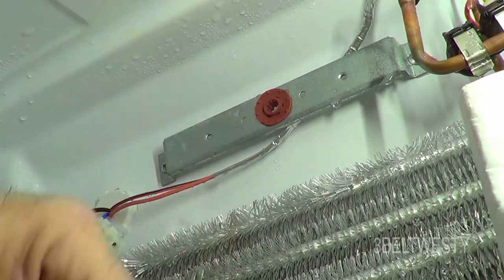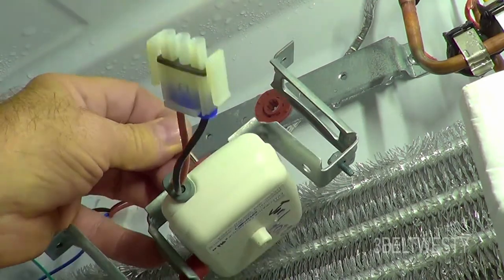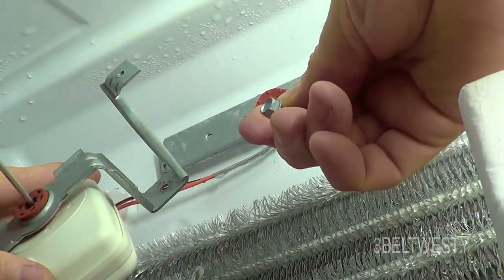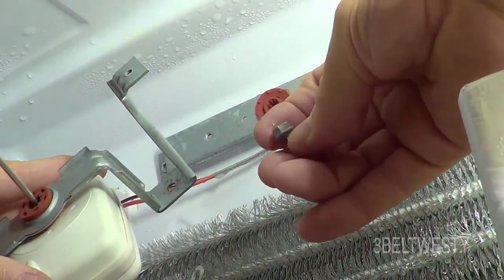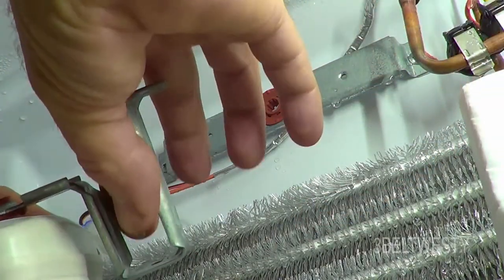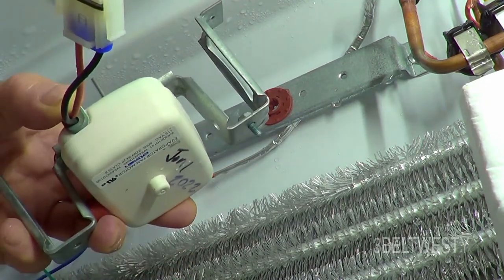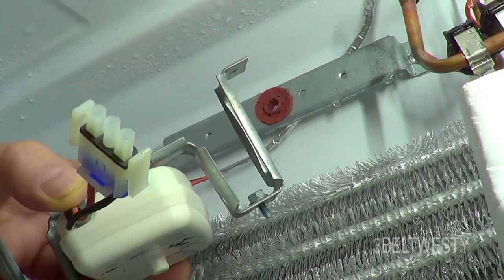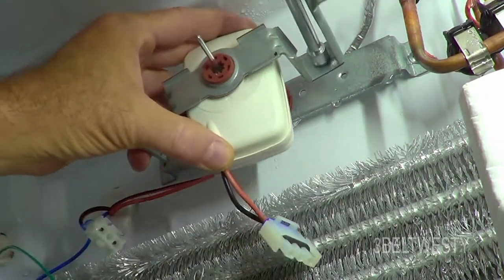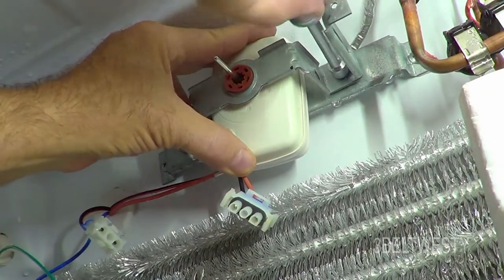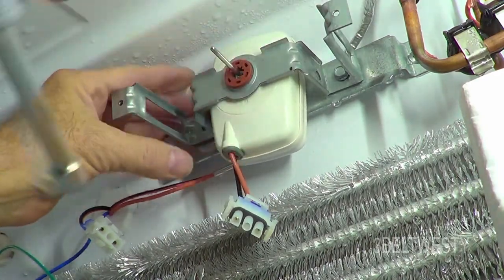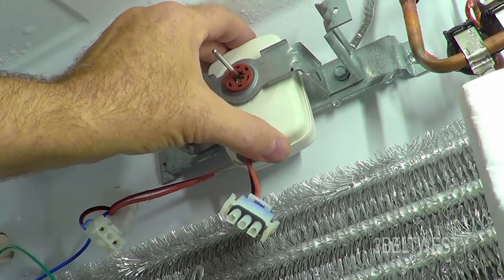Okay, I've got the new motor here in the bracket. It's got a rubber piece in the front. And I'm going to go through and have the connector facing down. The screws on this have our 8mm, 5/16ths hex. And I've got purposely, I've got the fan blade off. So I'm going to put the screw in here like this. And I've got to make sure I've got the right nut driver. There's an 8mm. I'm going to tilt this up. And those are self-tapping sheet metal screws. So there's one that's in there. So this is all held in rubber like this. You can tell the screw that goes on there that there's no Phillips on there. It's got to be snugged down in place.